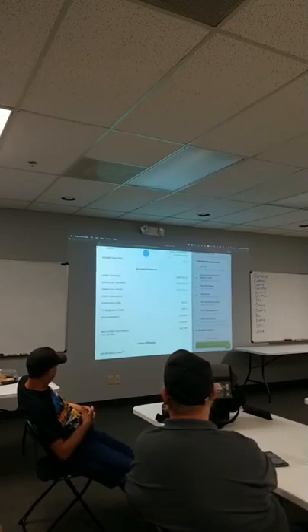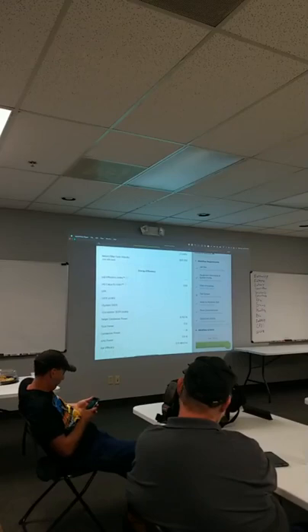Those are all the air side performance. Yep, so we've redone these so that they're boxed in. So here's your capacity calculations, your air side performance, your temperature split, your target temperature split, dehumidification in pounds per hour and gallons per hour. The software is calculating the filter face velocity, so it's looking at how fast the air is moving across the filter. And then also, if you input electrical data, there's an efficiency index and a capacity index. So basically what we're doing is calculating, if you look there, you can see the target condenser power of how many watts. We actually calculate how much capacity the machine's doing, how much efficiency it's doing, but these have to be tied in with electrical for those to read. And also your fan efficacy.